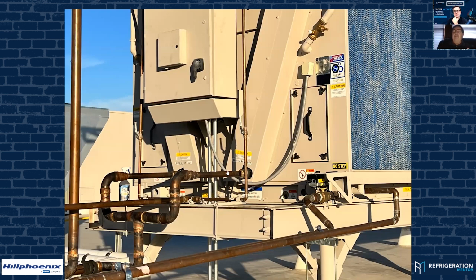And the reason I say PVC wrap is we want to keep the insulation from getting wet, because if it gets wet, it's useless. Three quarters of that sensor is in contact with the Rubatex, and only one quarter is in contact with the pipe. So if the Rubatex gets wet, it's going to affect the sensor more than the pipe. The white will also keep the rain from getting to it and the heat from affecting it as much. And on most of the older jobs I go on that are having problems, the first thing I check is where this is landed and how it's insulated.